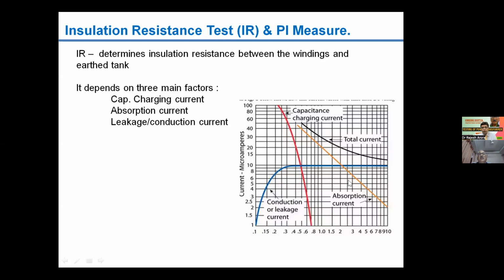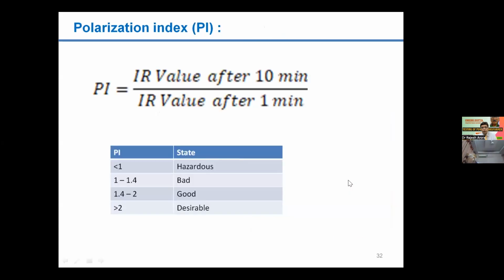And another standard discusses the PI also, how the PI should be. If it is near 1, then it is questionable. If it is 1 to 1.4, it is bad. If it is 1.4 to 1.6 or 1.7, we may say it is fair enough, but generally it should be more than 2. If it is more than 1.8, we may say it is good or desirable. Next.